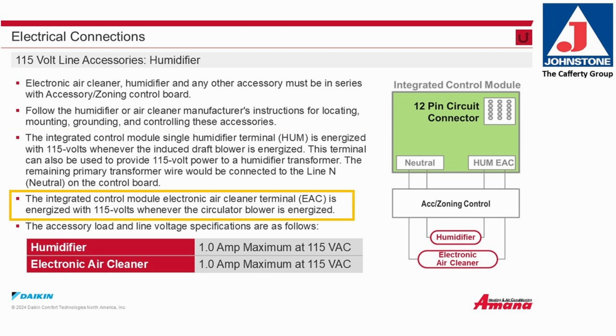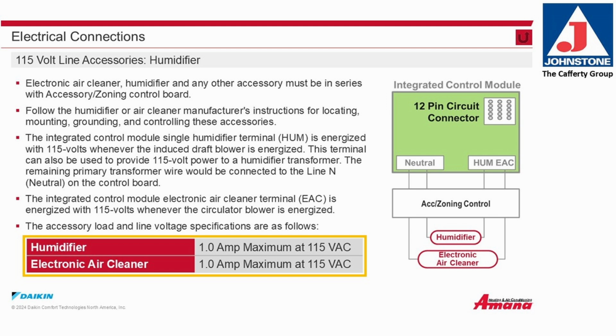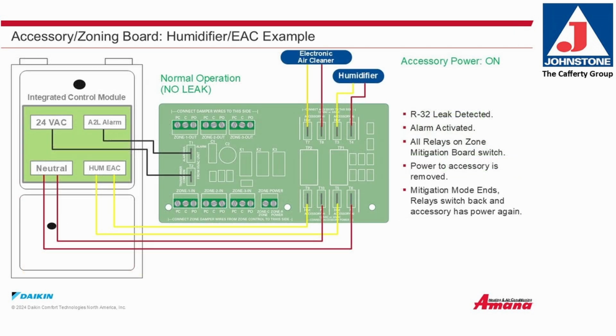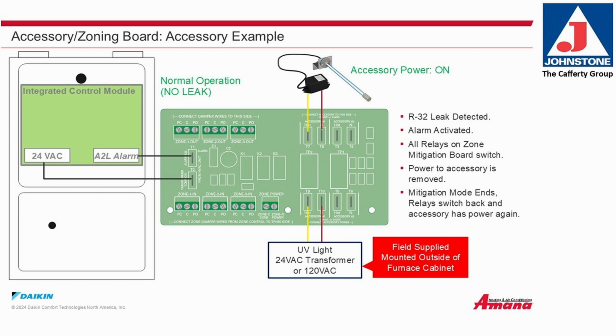The Integrated Control Module Electronic Air Cleaner Terminal, designated EAC, is energized with 115 volts whenever the circulation blower is energized. The accessory load and line voltage specifications are as follows. Both the humidifier and the electronic air cleaner terminals are limited to 1 amp maximum current at 115 volts AC. Here is a diagram showing the accessory/zoning board connections to the integrated control module using the example of humidifier and electronic air cleaner connections. Here's an accessory/zoning board connection example to the integrated control module with the example of a UV light connection. There would be a field-supplied transformer mounted outside of the furnace cabinet.